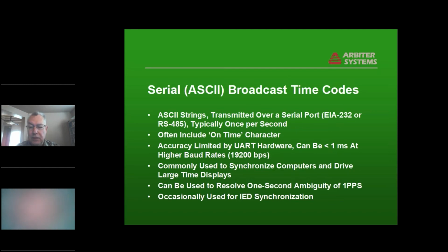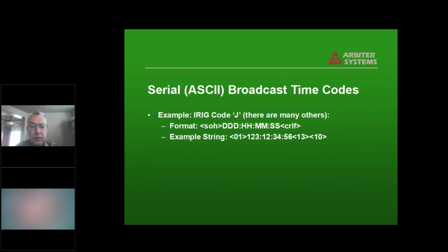As a matter of fact, when you get a time out of a GPS receiver module, a little chip these days, inside of one of our clocks, it comes out as a 1 PPS signal and a serial time message. These have been used for IED synchronization, but more and more these days, other methods are being used. This is an example of what a serial ASCII time code looks like. IRIG standardized on IRIG code J, which is a serial time code. IRIG B codes are the sine wave and pulse codes that I showed you earlier, but code J is an ASCII time transmitted over RS-232 or RS-485. The start of header character 01 is the on-time character, followed by day, hour, minute, and second, and then a carriage return line feed, and that's repeated every second.